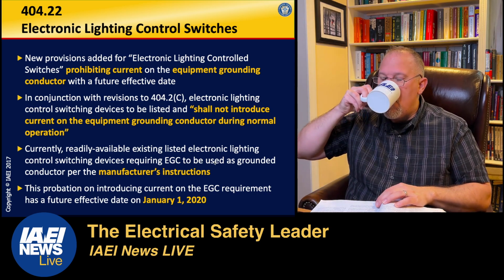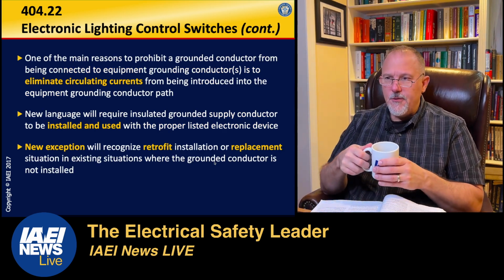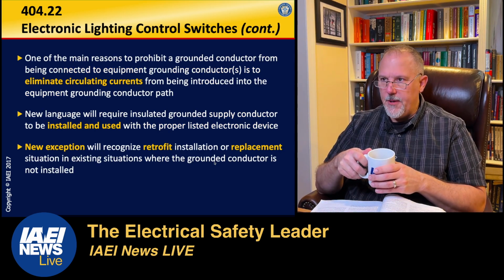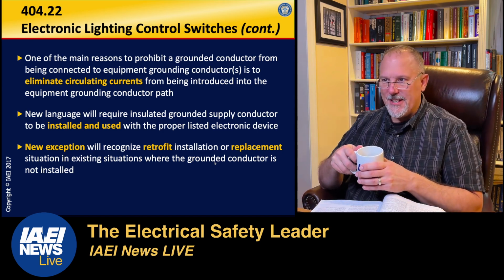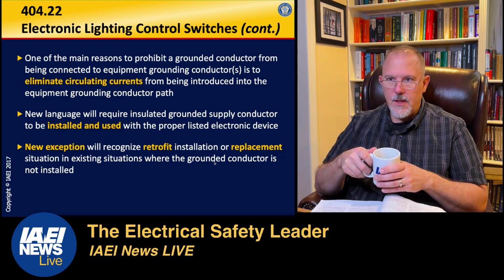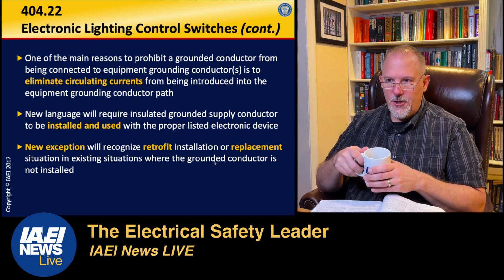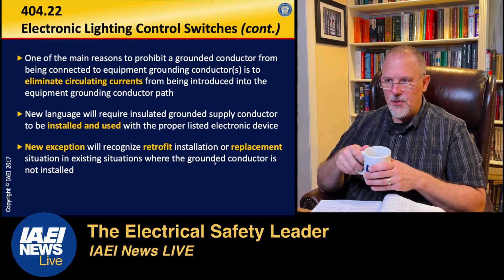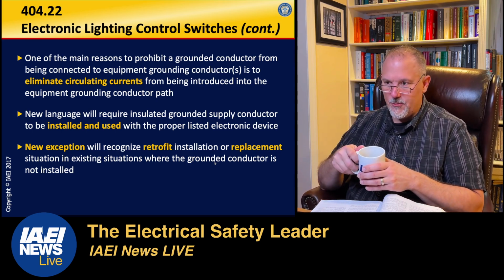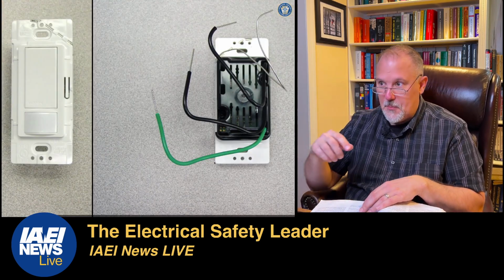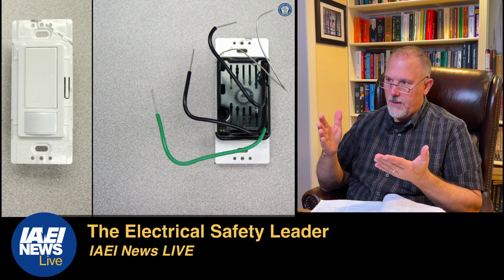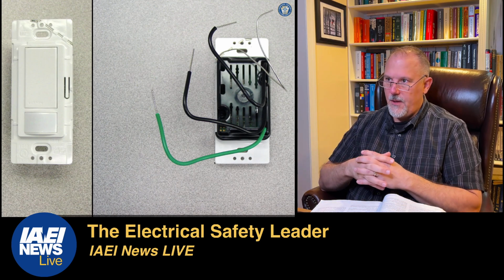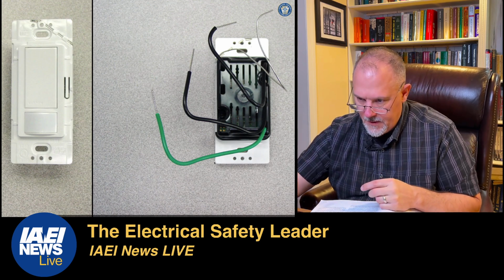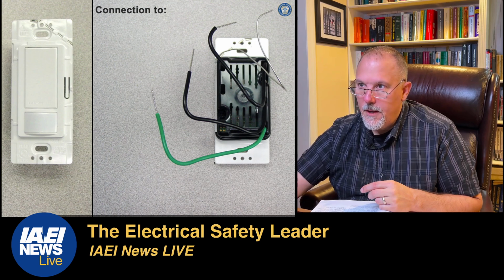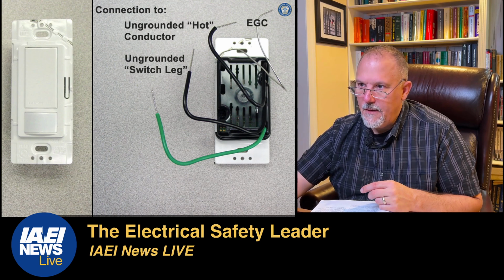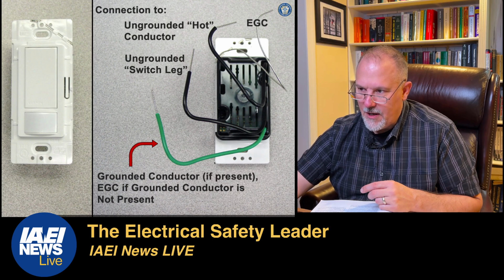Okay, so one of the main reasons, I love this. One of the main reasons to prohibit a grounded conductor from being connected to the equipment grounding conductors is to eliminate circulating currents from being introduced into the equipment. New language will require insulated grounded supply conductors to be installed and used with the proper listed electronic devices. New exception will recognize retrofit. All right, and here is the picture. Now you think you've got to install this thing, and you want to make sure you have all the right conductors terminating there. EGC, there's your hot, there's your ungrounded switch leg, and that's your grounded conductor.